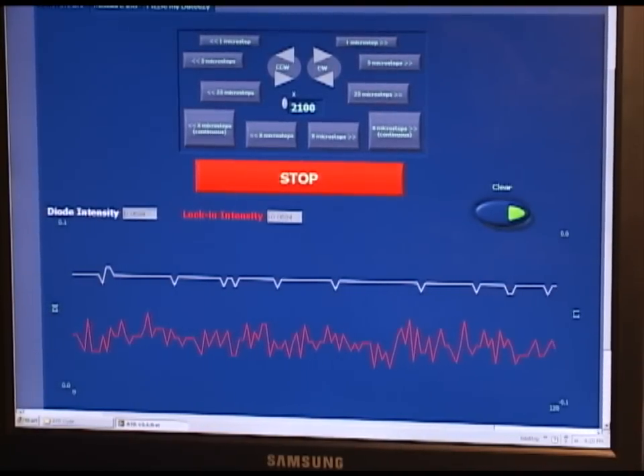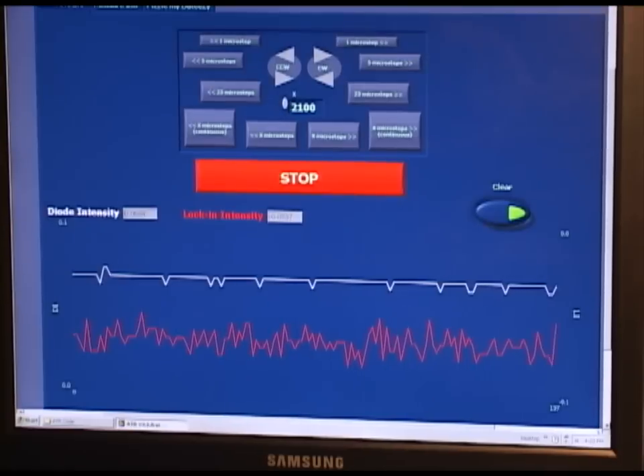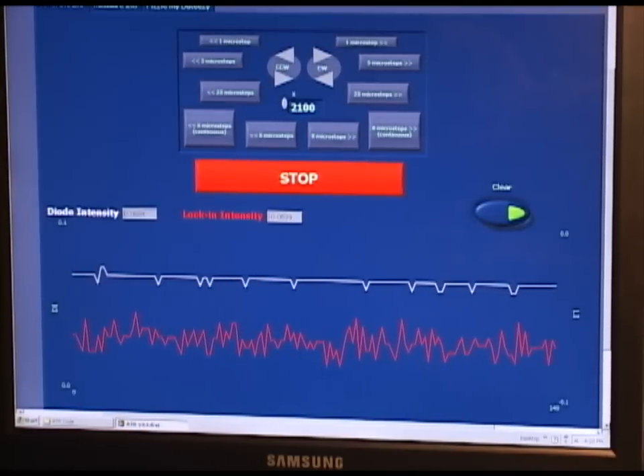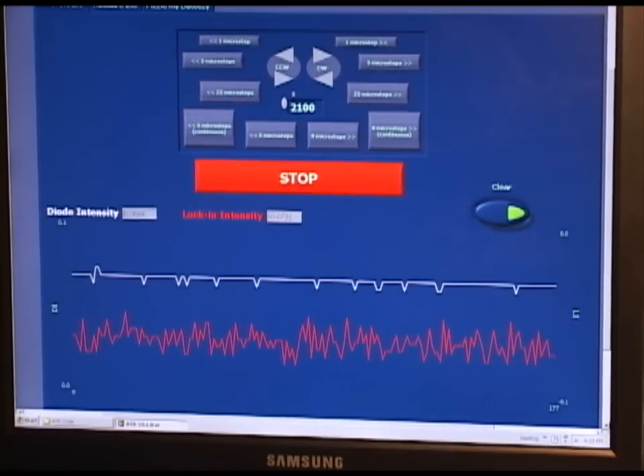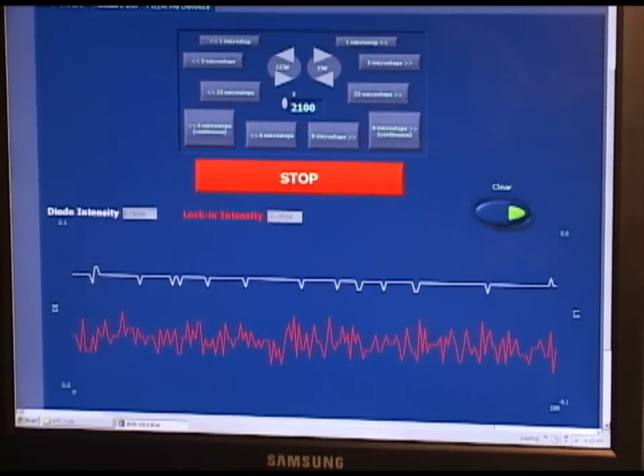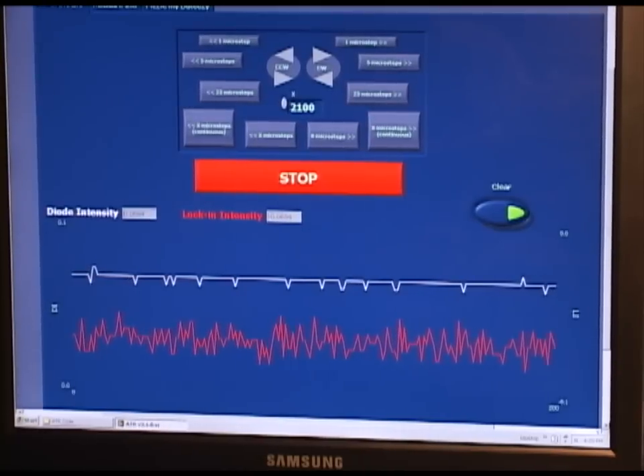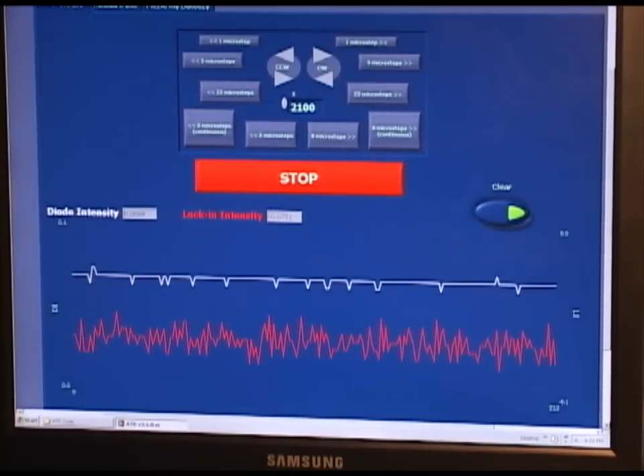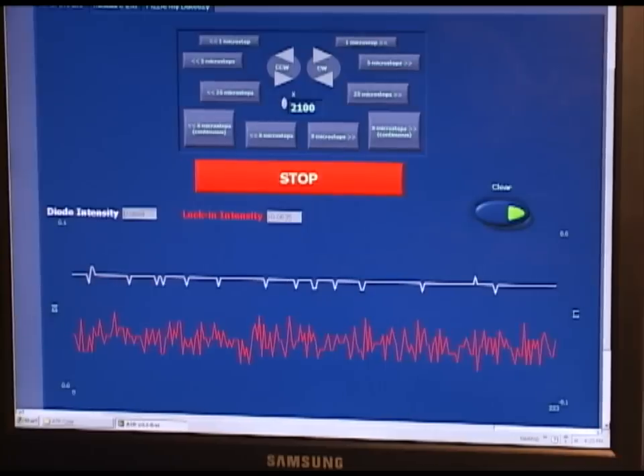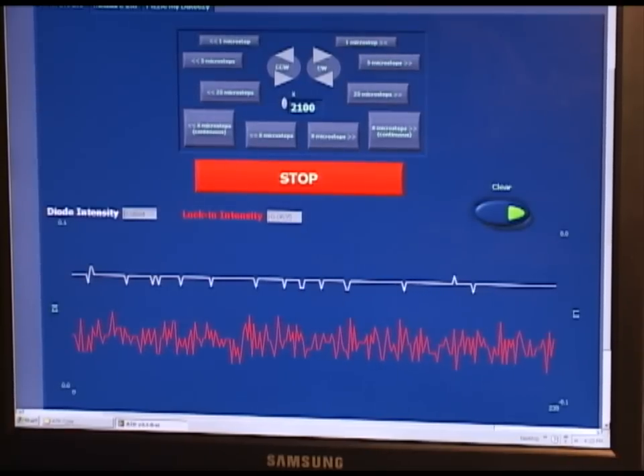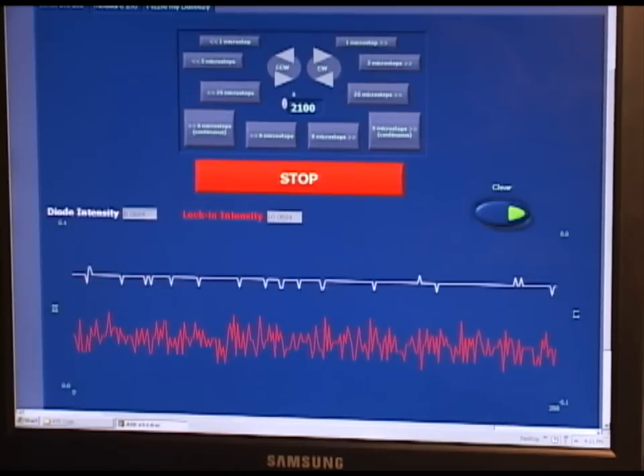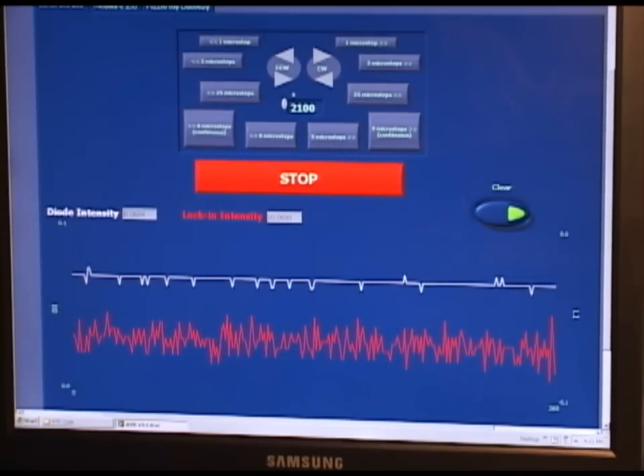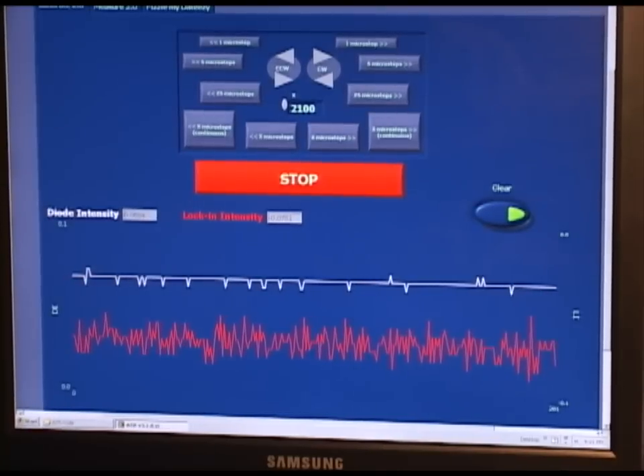Now we want to rotate the sample and prism setup to search for modes. Modes are points at which there is total internal reflection. These occur at what we call critical angles. So we will rotate the sample to find these critical angles. Once we have found a suitable mode, we begin calibrating. First, I will begin rotating the sample to search for a mode.